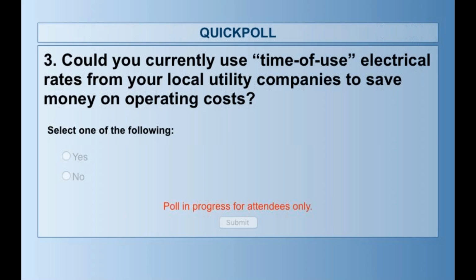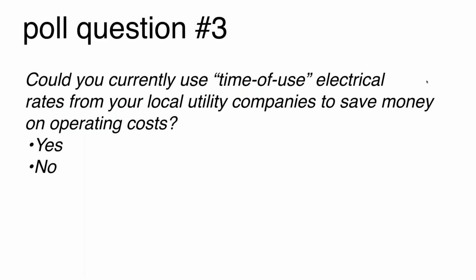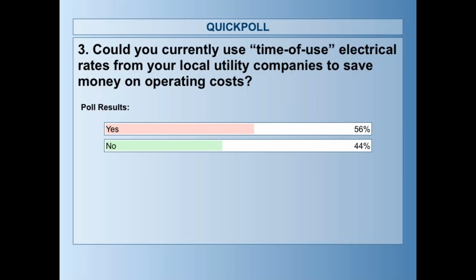Okay, so it looks like the votes are starting to trail off here, so let me share that. We asked, could you currently use time of use? We had a 56% yes result there. Like you're saying, John, I know that the heat pump water heater manufacturers are all working towards a shared communication network, basically called EcoPort, that would allow for real-time communication with the utility companies to respond to what's happening in the grid, not just to schedule, okay, turn it on at 6 p.m. because that's when the rate's better, but to be pretty dynamic. So that technology is coming with the policy support and then manufacturer support that could work just as well for an air-to-water heat pump.